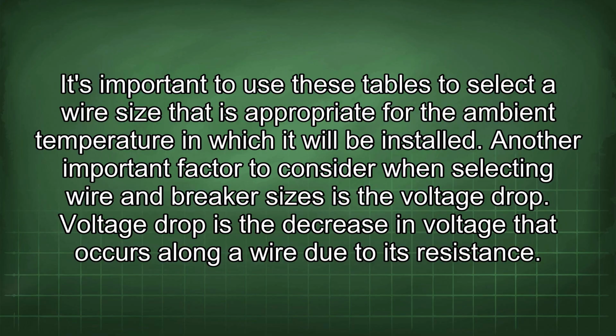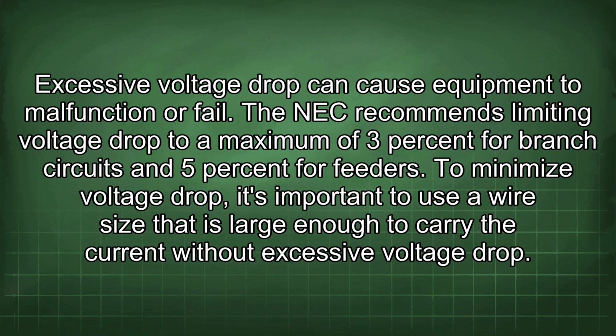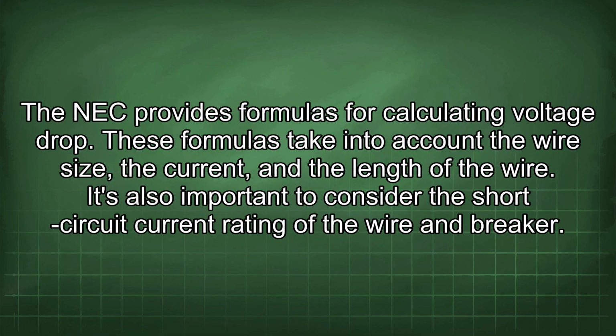Voltage drop is the decrease in voltage that occurs along a wire due to its resistance. Excessive voltage drop can cause equipment to malfunction or fail. The NEC recommends limiting voltage drop to a maximum of 3% for branch circuits and 5% for feeders. To minimize voltage drop, it's important to use a wire size that is large enough to carry the current without excessive voltage drop. The NEC provides formulas for calculating voltage drop. These formulas take into account the wire size, the current, and the length of the wire.